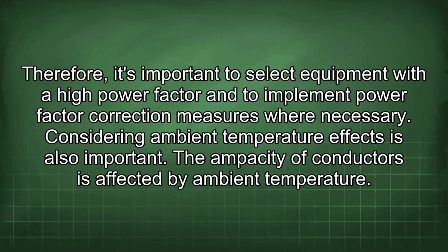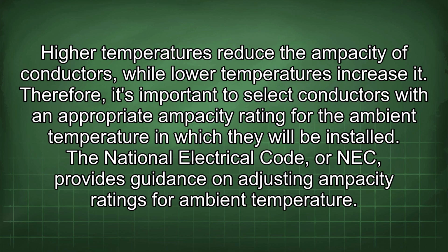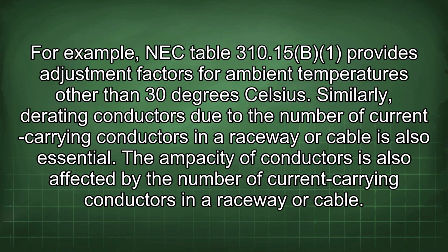Considering ambient temperature effects is also important. The ampacity of conductors is affected by ambient temperature. Higher temperatures reduce the ampacity of conductors, while lower temperatures increase it. Therefore, it's important to select conductors with an appropriate ampacity rating for the ambient temperature in which they will be installed. The National Electrical Code, or NEC, provides guidance on adjusting ampacity ratings for ambient temperature. For example, NEC Table 310.15(B)(2)(a) provides adjustment factors for ambient temperatures other than 30 degrees Celsius.